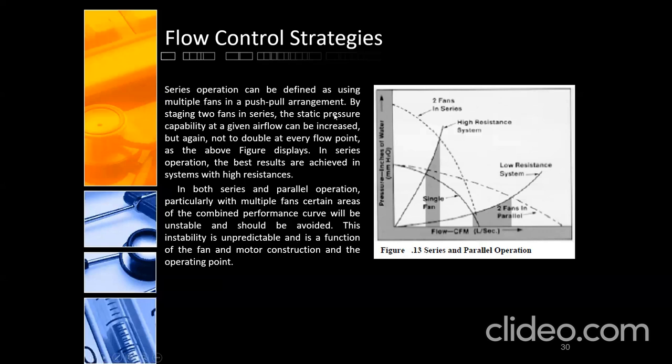Series operation can be defined. Ito ang series. As using multiple fans in push-pull arrangement. By staging two fans in series, the static capability at a given airflow can be increased. Yeah, tapos nag-increase yung head. So, isang flow lang, isang flow. Dito, punta doon. But again, not to double at every flow point.